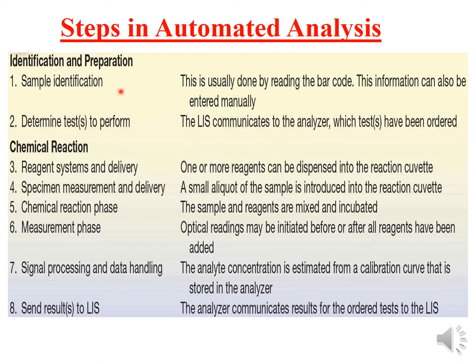This can be done by barcode or manually, depending on the facility available in the lab. We then determine the tests, feed them into the computer, and the analysis part starts — that is the reagent system delivery, specimen measurement and delivery, and chemical reaction phase.